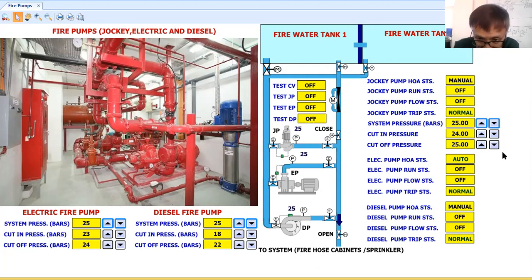Okay, now guys, the sprinkler heads are fusible. So how does it work? With these fusible links, there will be some temperature setting there. Okay, so I'm not very comfortable stating the temperature at which your sprinkler head will burst or give in. Now in one of my projects, we encountered a sprinkler head installed in a cooler. I think the refrigeration system had some problem, and it created a small fire. Then the sprinkler head burst. Then our fire pump ran. Okay.